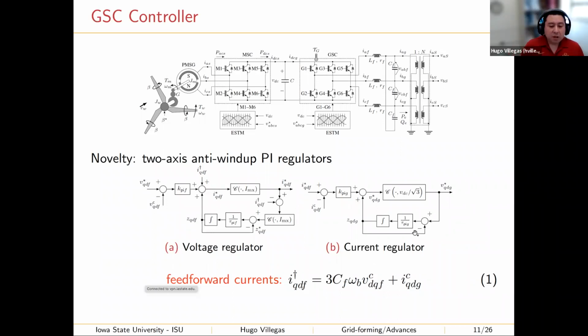Especially in this voltage regulator, current regulator setup, it was necessary because the voltage regulator outputs current commands and the current regulator outputs voltage commands. The current commands output by the voltage regulator are limited, for example, by the rating of the converter, whereas the voltage commands output by the current regulator are limited by the amount of DC link voltage present at that particular point in time. If there is some violation in those variables, there could be overcurrent problems, or in the case of the DC link voltage, controllability problems.